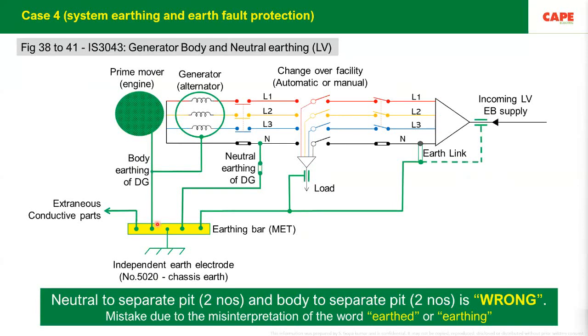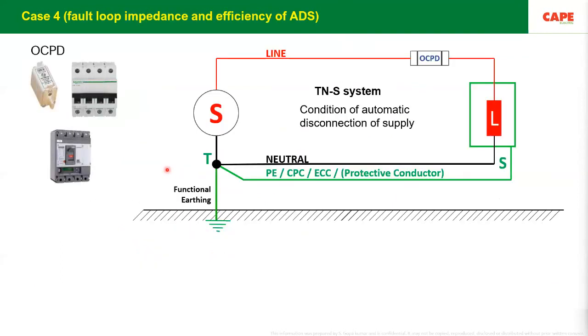Which is called the Code of Practice of Earthing, figure number 38. You can find out how to make the earthing and earth fault protection in a DG. Then you see, if there is an earth fault, the system shall be designed in such a way that the fault current quickly returns back to the source. Once the fault current quickly returns back to the source, enough fault current flows and it disconnects the protective device. The protective device will be very efficient.